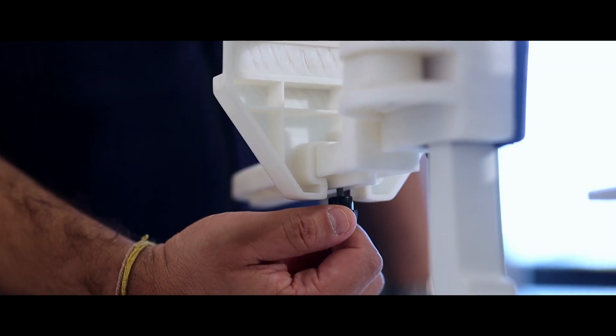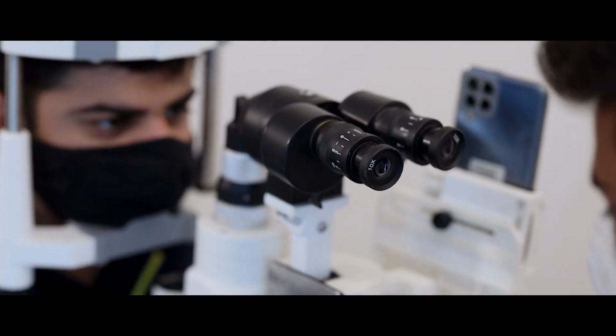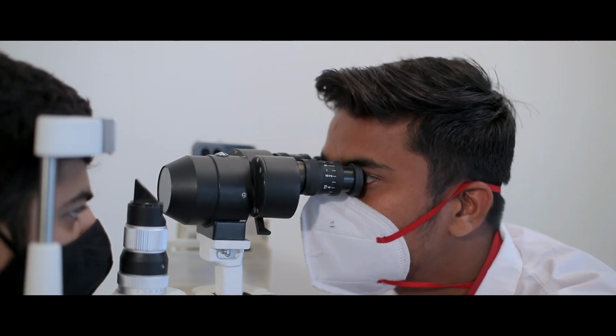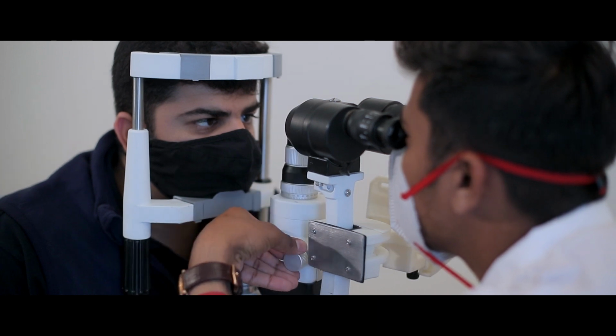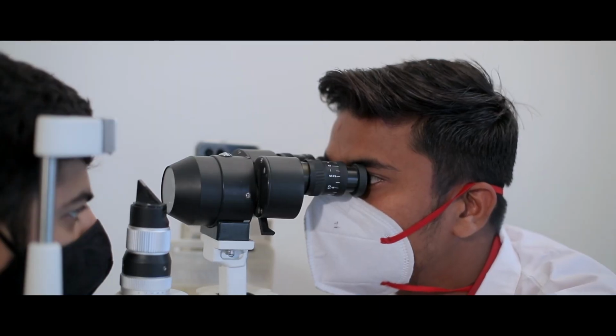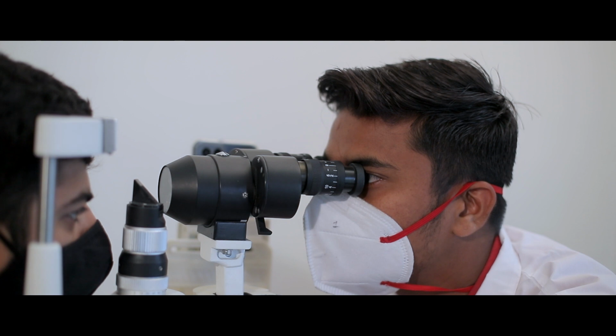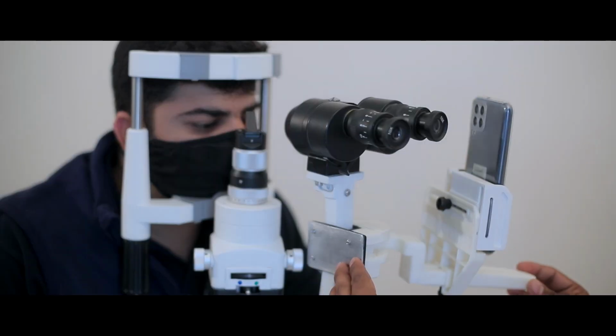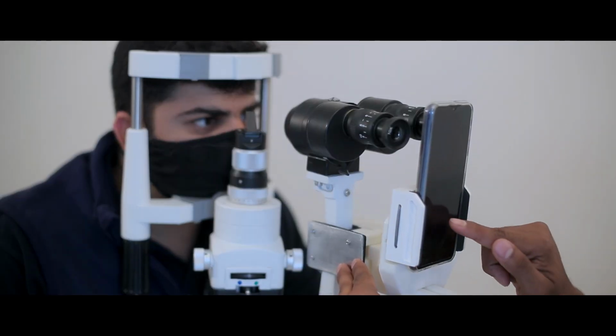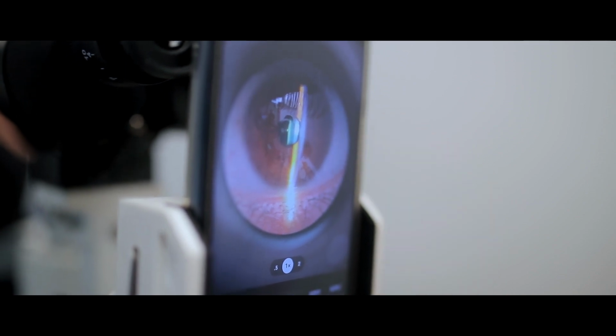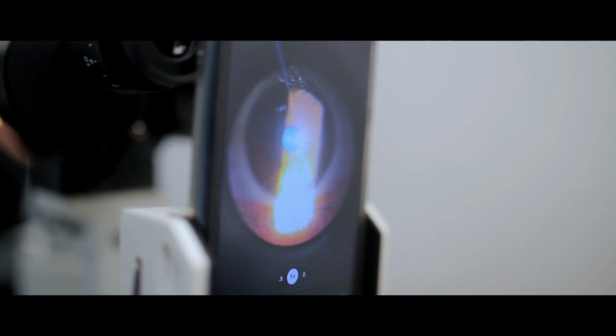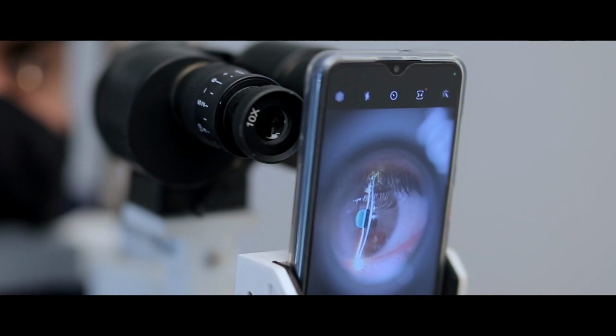Fix the assembly onto the slit lamp by tightening the screws. The device is now permanently installed on the slit lamp. The operator is doing a routine slit lamp examination without any interference. Rotate the device into the right eyepiece of the slit lamp and open the camera app to capture images or videos of the eye exam.